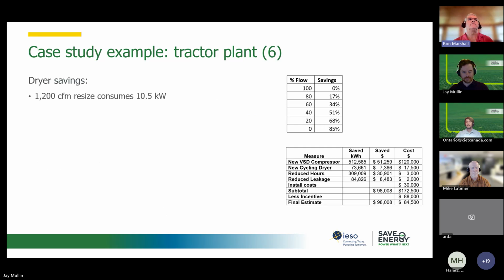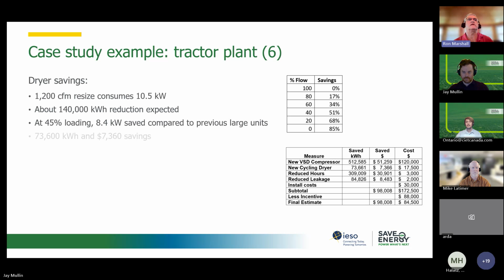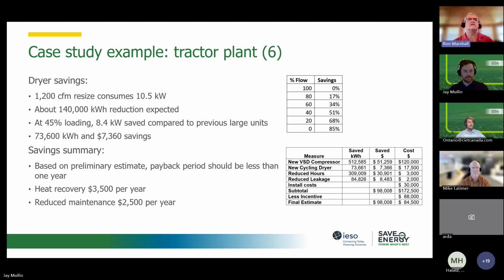Next slide. Right, so dryer savings, they resized the dryer, purchased cycling dryers that turned themselves down, especially when the compressor system was off. They expected 140,000 kilowatt hours. We did a verification measurement, and we found that the savings wasn't exactly what we expected because they didn't fix as many leaks as they could. So the last measurement, they were still working on leaks, right? So the savings summary, we can see that pretty significant savings were gained by putting in a variable speed drive, cycling dryer, reducing the operating hours, reducing leakage, and getting a really nice $88,000 incentive from the power utility, right? So a very attractive savings project in this case.